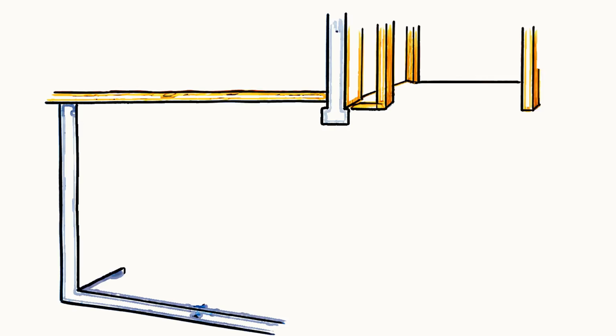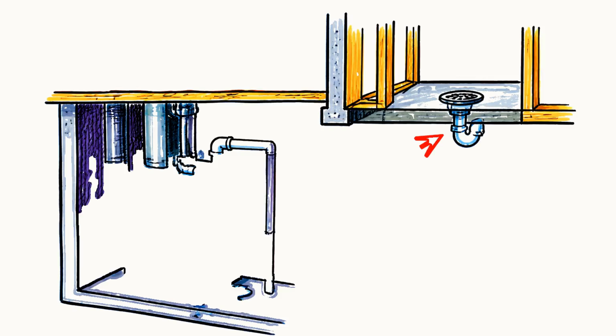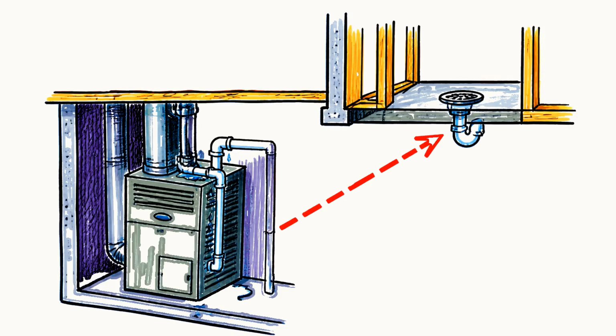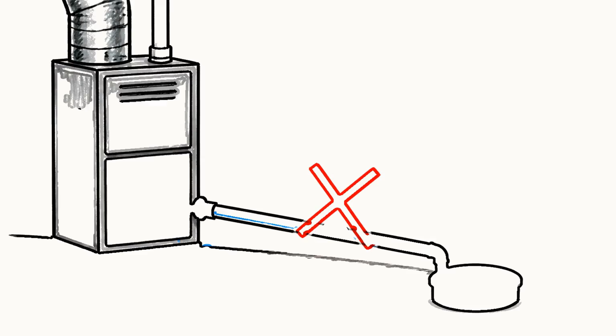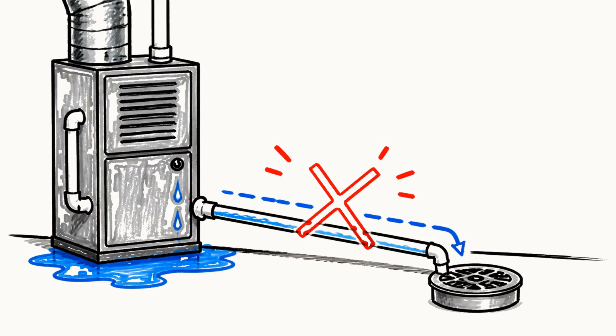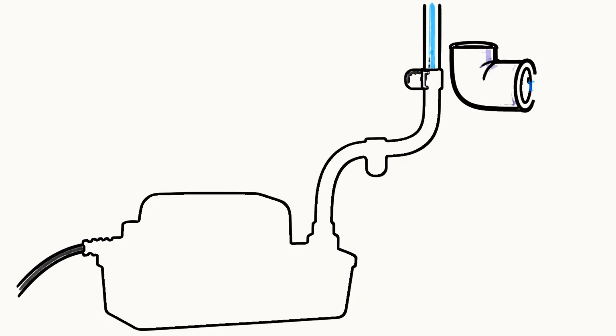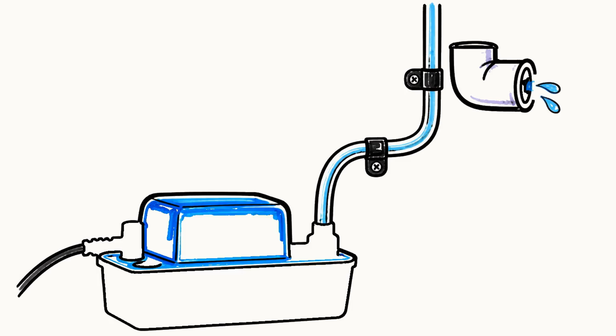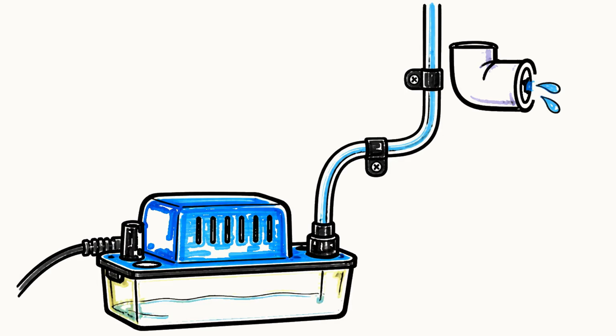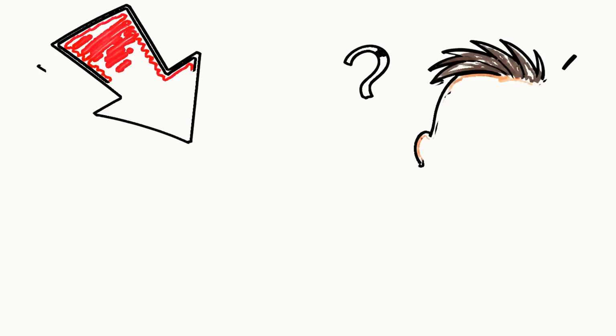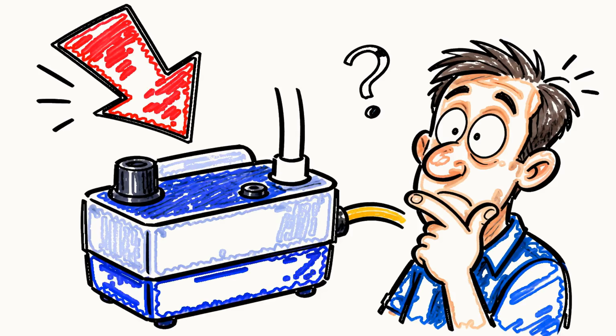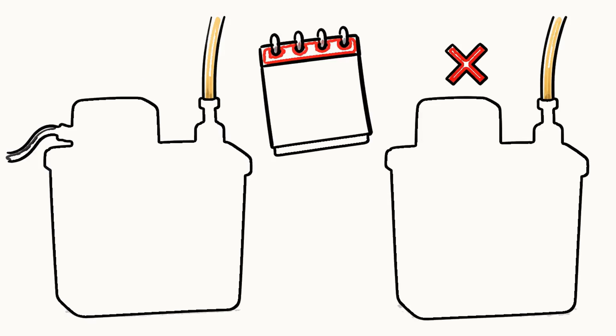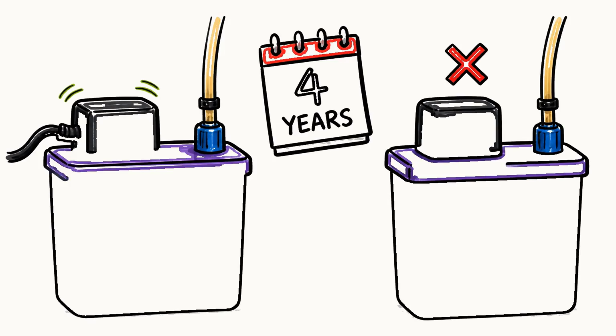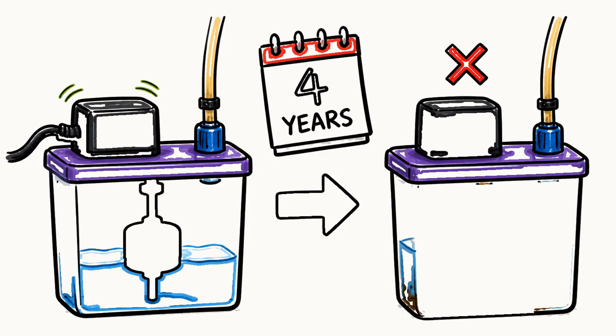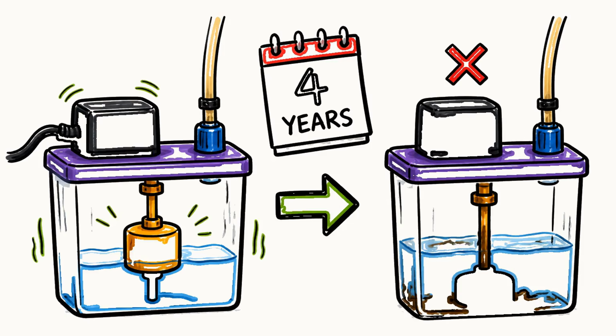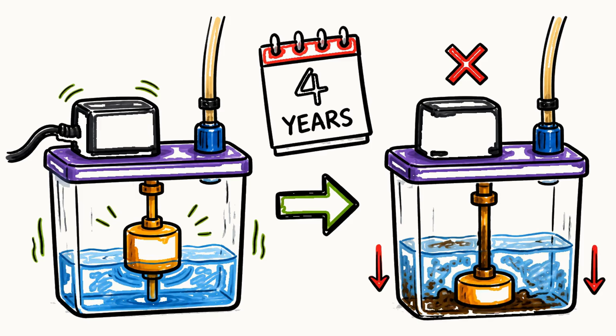The third cause shows up only in homes where the furnace sits below the drain or too far from one. In that case, the water cannot flow out by gravity, so there is a small condensate pump doing the lifting, a little box with a motor and a thin discharge tube climbing up to a drain. This is the one that fools people. A pump like a Little Giant runs fine for about 4 years. Then the plastic float inside gums up and sticks in the down position, and the motor stops getting the signal to switch on.